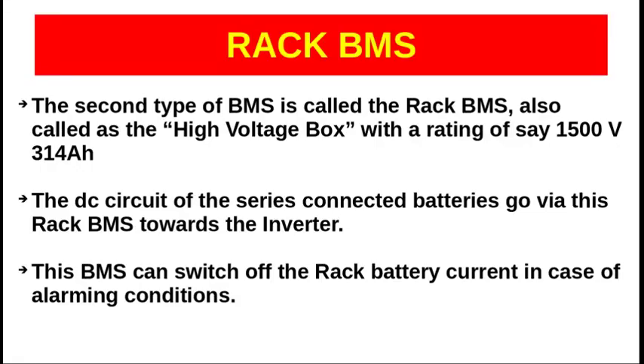Rack BMS. The second type of BMS is called the rack BMS. It is also called as the high voltage box, with a rating of say 1500 volt, 314 ampere hour. The DC circuit of the series connected batteries go via this rack BMS towards the inverter. This BMS can switch off the rack battery current in case of alarming conditions.